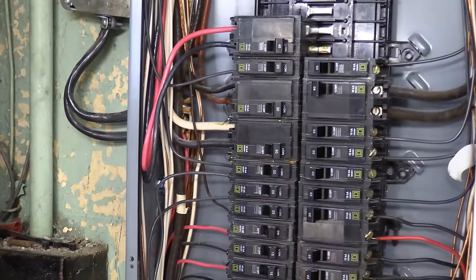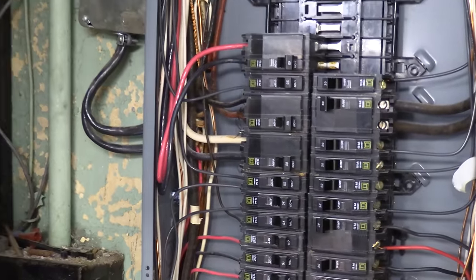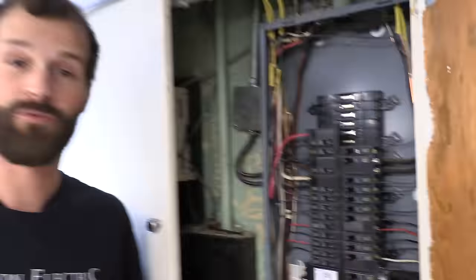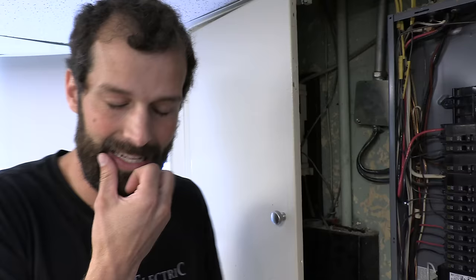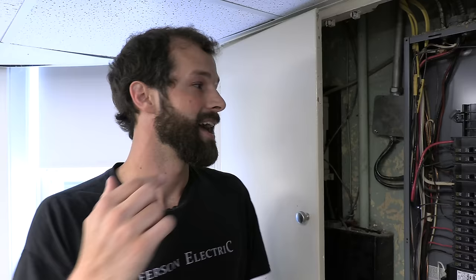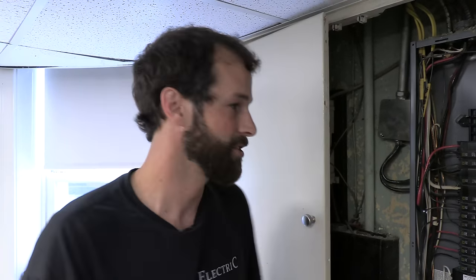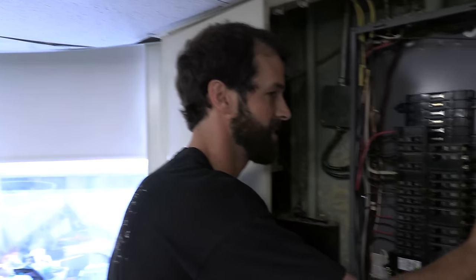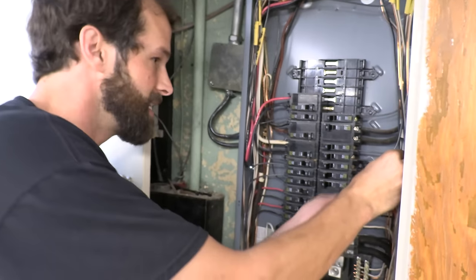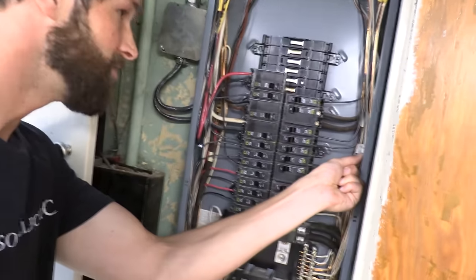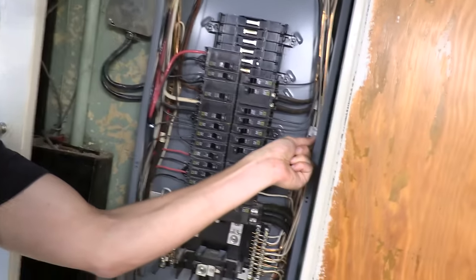Occasionally, there'll be a circuit that's maybe a spare that's run and it's up in the attic. See, a lot of times when we do a bathroom remodel, for instance, on the second floor, and when we're pulling a new 20 amp circuit upstairs in like an older home where there previously was not a dedicated circuit, we'll pull an additional 14 and 12 gauge circuit to the attic, coil up a little extra, put them in a J box so they're properly terminated, and now we've got capacity for an attic finish out down the road. If one of those circuits is here, if there's any indication that was left by the electrician, such as this electrical tape here that says Unfinished Base. Sounds like a circuit to the unfinished basement. And that's been capped off and left behind. So I'm looking for any identifier such as that.